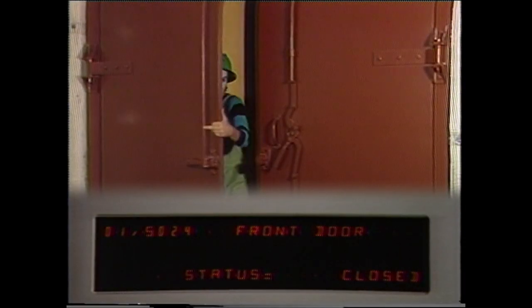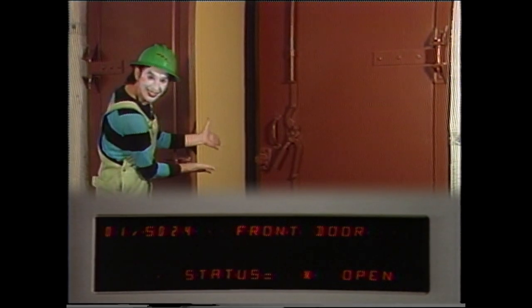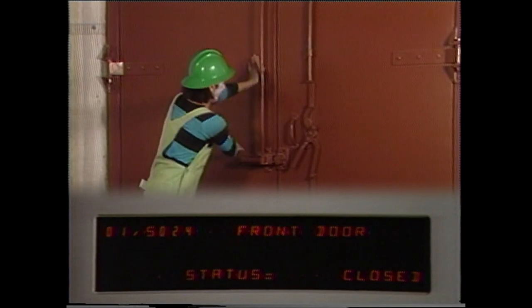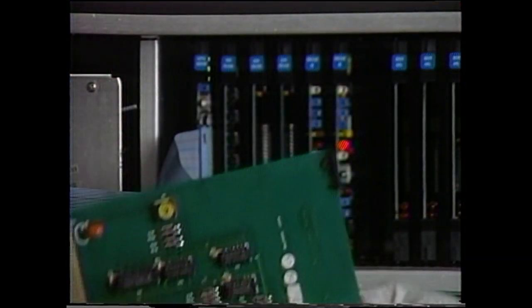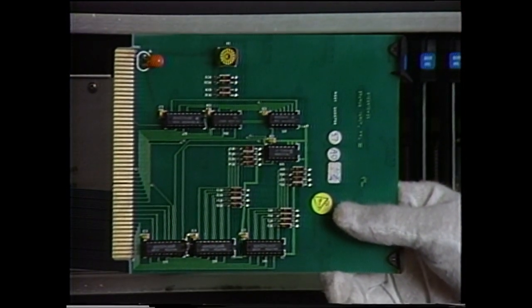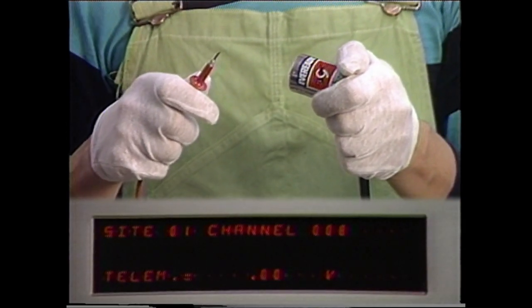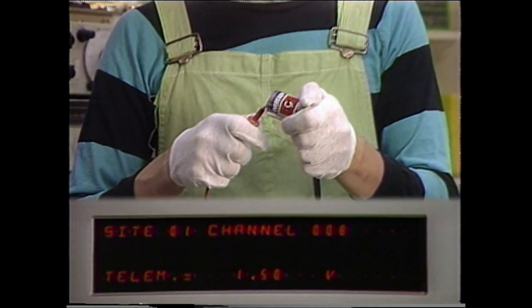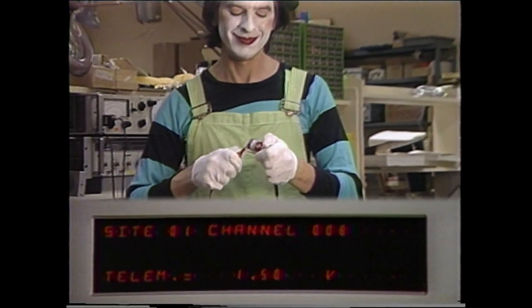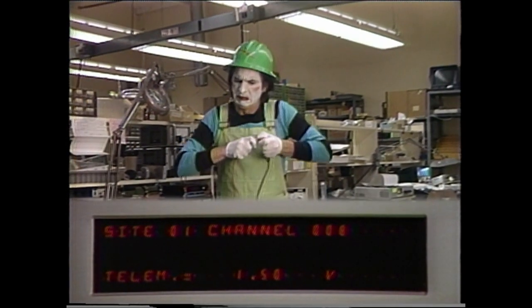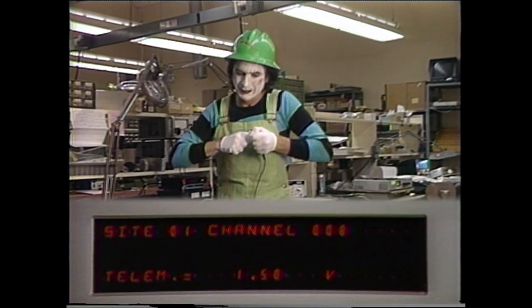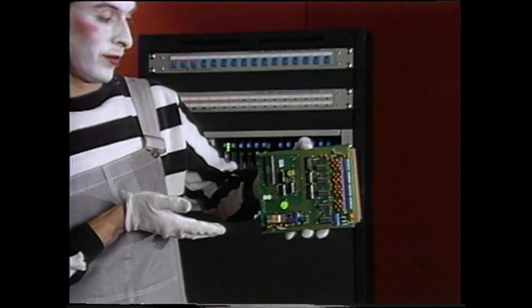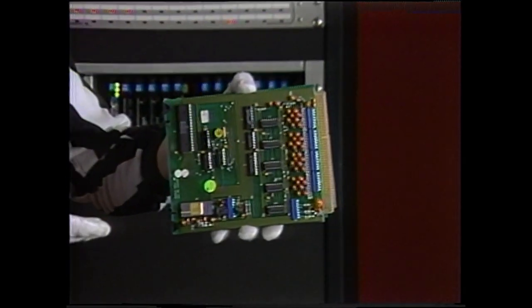Each command module provides 16 command outputs. Status inputs accept contact closures or voltages to indicate on or off, or any other two states of the devices being monitored. Each status module provides 16 status inputs. Telemetry inputs accept sample positive or negative DC voltages from 0.25 to 5 volts, which are proportional to the actual parameters being monitored. These telemetry values are calibrated during system setup. There are 16 telemetry inputs for each telemetry module used.